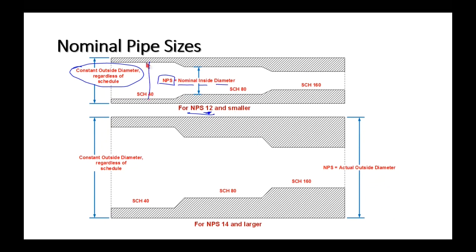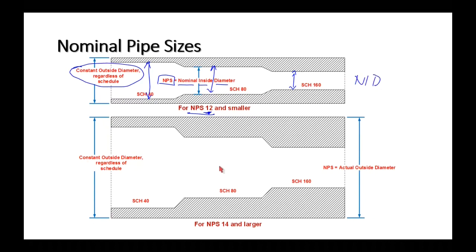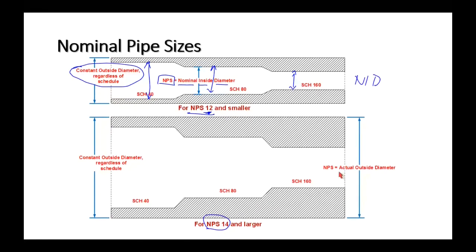For NPS 14 and larger, the NPS number refers to the actual outside diameter. So NPS 14 pipe has an actual outside diameter of 14 inches. It's still a constant OD regardless of schedule — but for large pipe, it's the actual OD, not a nominal inside diameter reference.